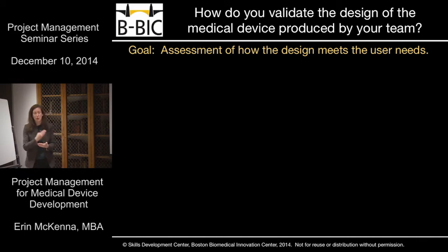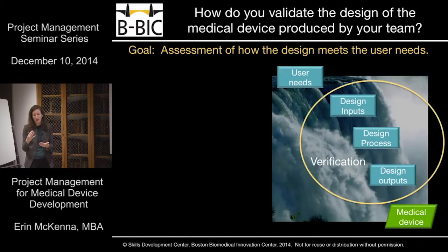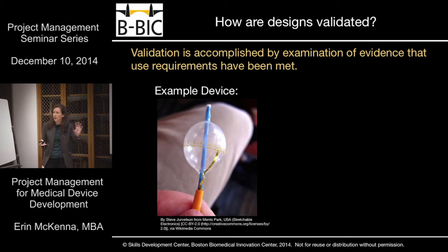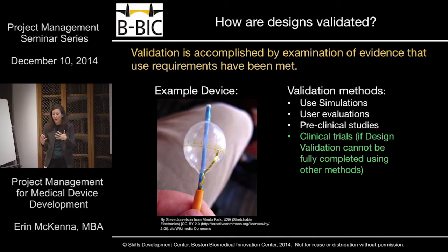The other element that you do once you've completed that is what's called the design validation. If you've shown that your design outputs will meet your design inputs, in theory, what you should get is a medical device that meets your user needs, but you still need to show that it does. Because we're talking more qualitative, we're talking about some different assessment methods than under verification. While verification is a lot of validated test methods, numbers, and data analyses, validation methods are more focused on use simulations.